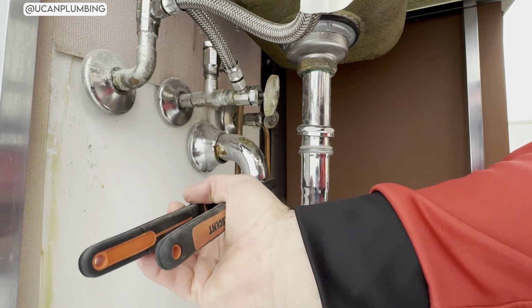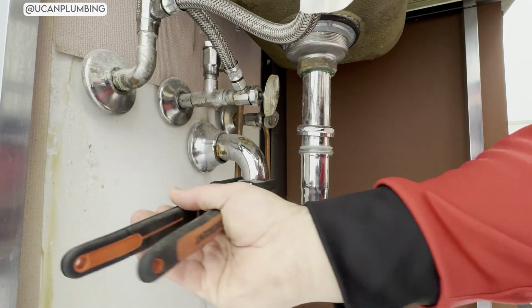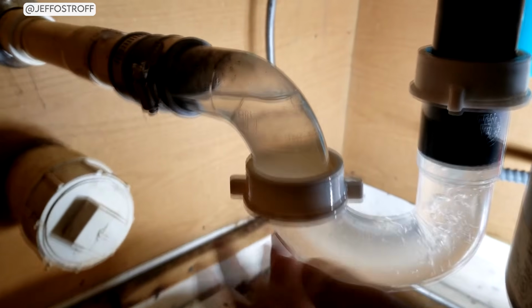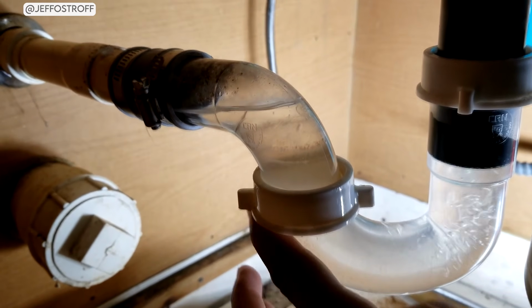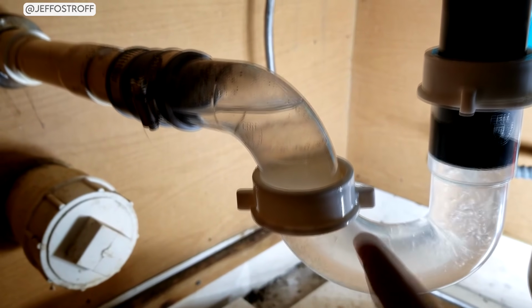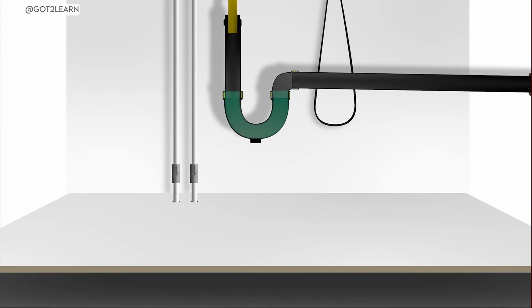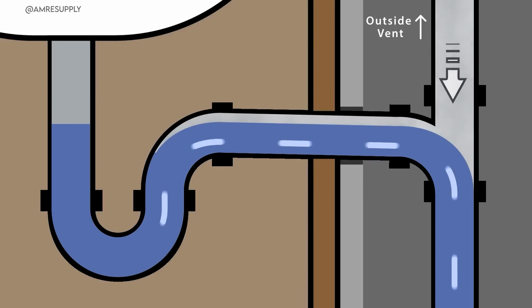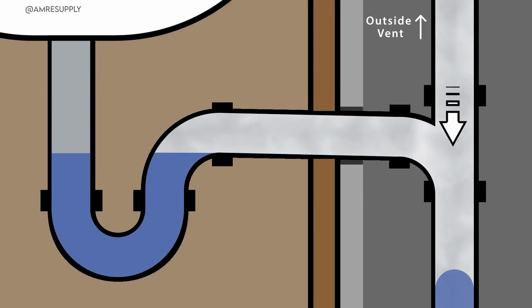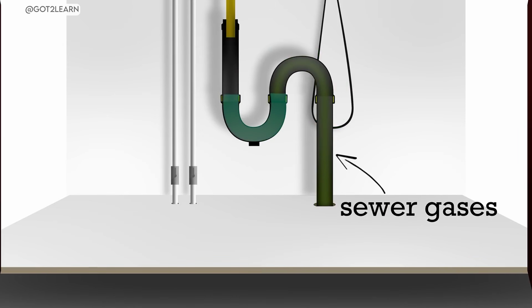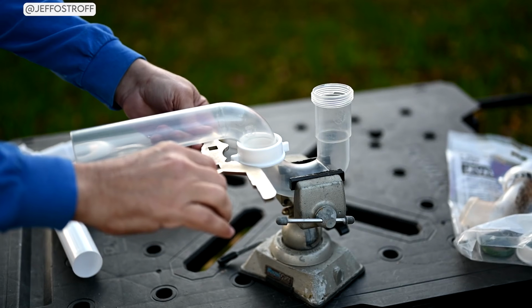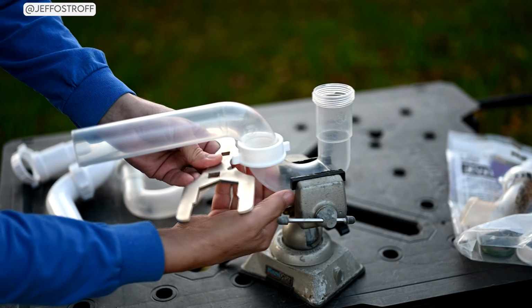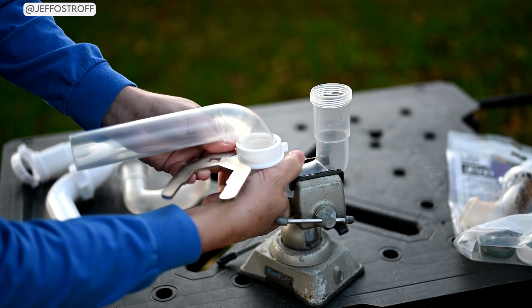The vent pipe allows air into the system so that when water drains, it flows freely without creating the vacuum that causes siphoning. The P-trap's design makes it almost impossible for the water seal to get sucked out during normal use. That single difference in direction, down versus back, is the entire reason one trap is banned and the other is required in every modern plumbing code.